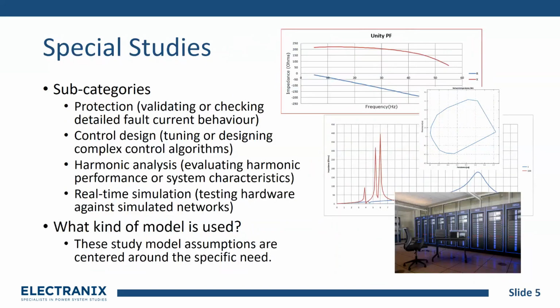Then we have a category of what I would say are special studies. So these are where you have a specific thing that you need to figure out. It might be validating a protection, currents coming out of an IBR, or looking at control design of an HVDC link, or maybe you're doing harmonic studies in a region. I've got a picture in the bottom right-hand side of a supercomputer, essentially a real-time simulator, which is another category of EMT where you're testing hardware, actual control hardware or protection hardware, against a simulated network. So these models vary widely, and they're really very specific, and we're not going to talk about them much today. Next slide, Alex.